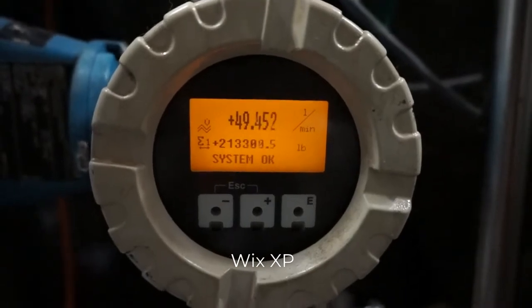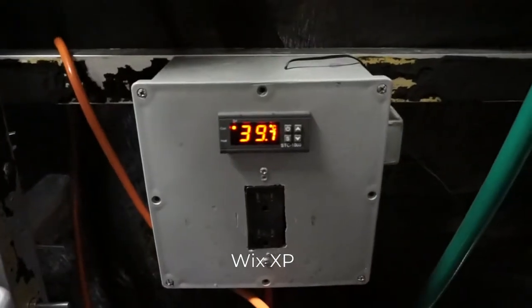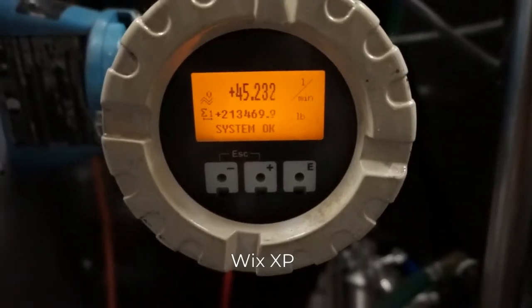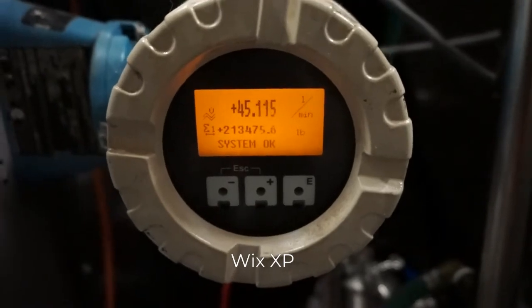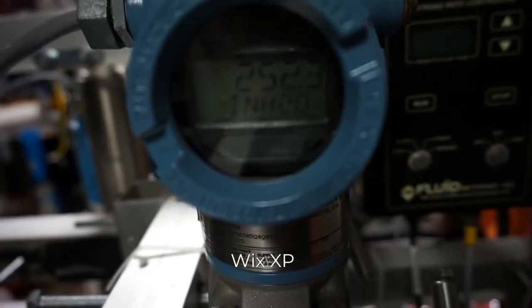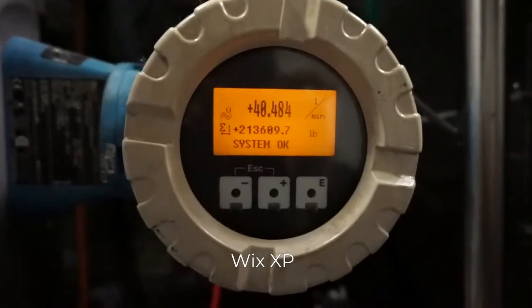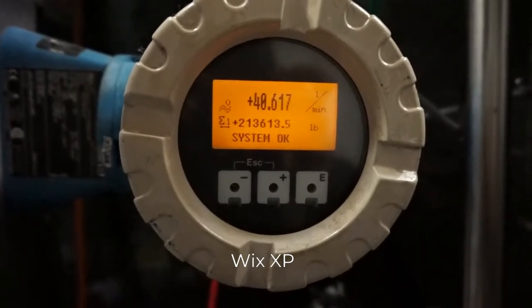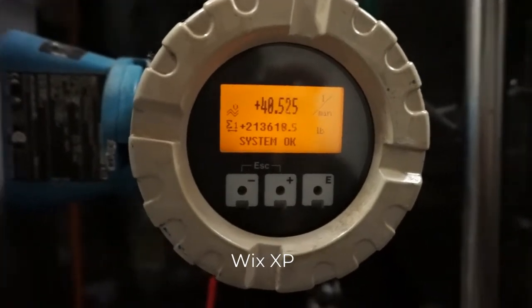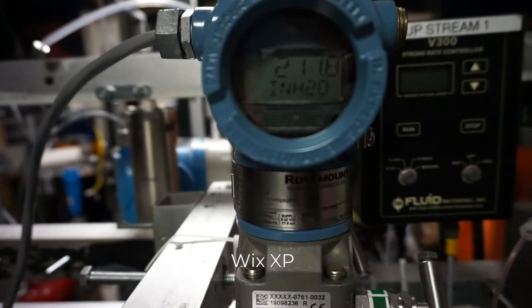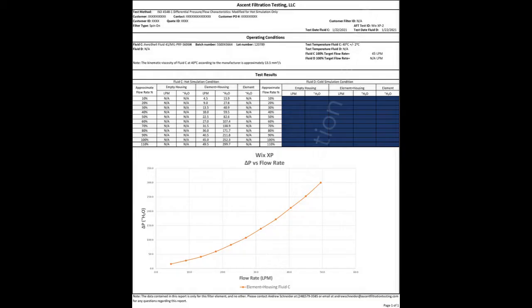Our first data point is 49.5 liters per minute — that's 110% of our flow rate — and we have approximately 299 inches of H2O on our differential pressure gauge. We are within our temp spec. Our second data point is 45 liters per minute, which is our 100% flow rate, at 252.3 inches of H2O. Our third data point is 40.5 liters per minute at 211.8 inches of H2O.